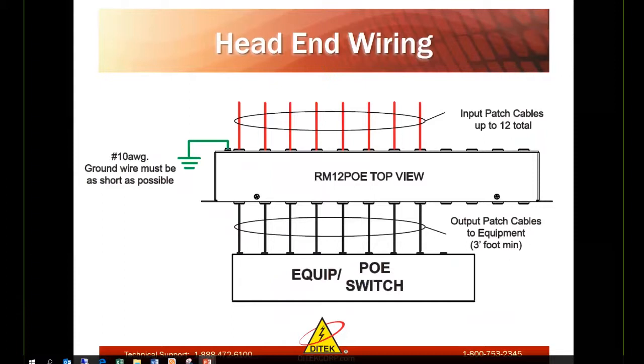Here, it's very critical. Just about every piece of equipment we make, we need to have at least an output patch cord or conductor to the equipment of 3 foot minimum length. It can be longer, but you do need that 3 foot whip, so that the device can basically react or have the response time to open a path to ground.